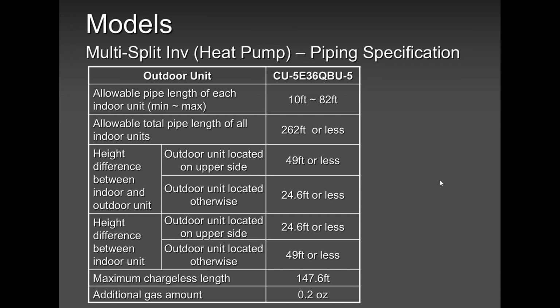Then comes the pipeline. These units have been in the lab for years before they got released. And I'm not joking. They have been released after testing of more than 5 years for pipeline, for height, all because they want to maintain constant efficiency, strength of that compressor, keeping in mind oil return. All that you see here, height difference, pipeline, you name it, all is about oil return.